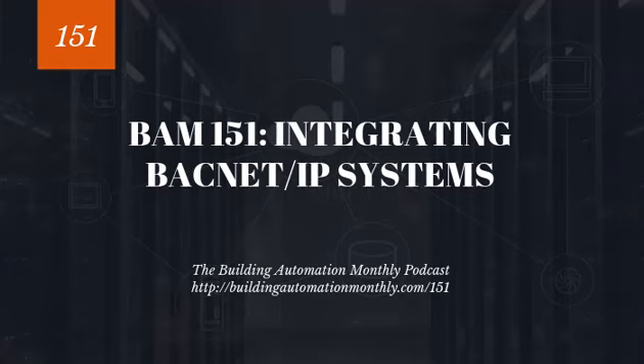So, as I was saying, BACnet is going to take those specific broadcast messages utilizing the BACnet Broadcast Management Device and the BDT, which, if I remember correctly, stands for Broadcast Distribution Table. I always mix that up, but it's something you can Google pretty easily. And what that table does is it's a list of all the BACnet networks.